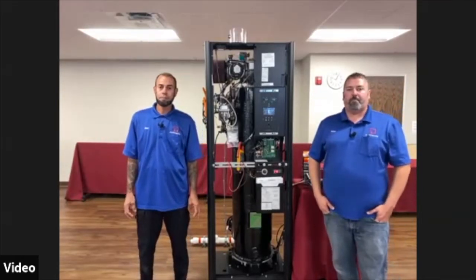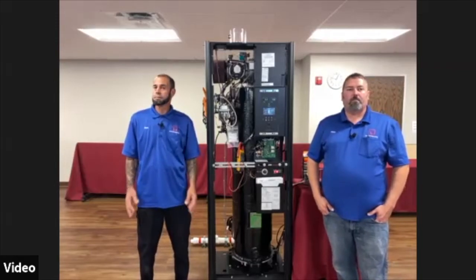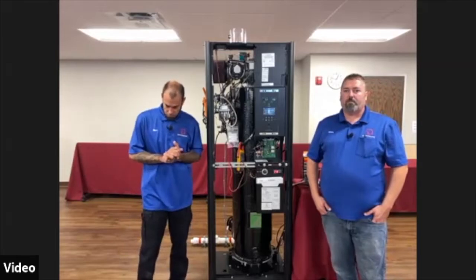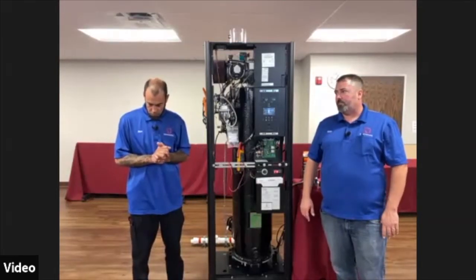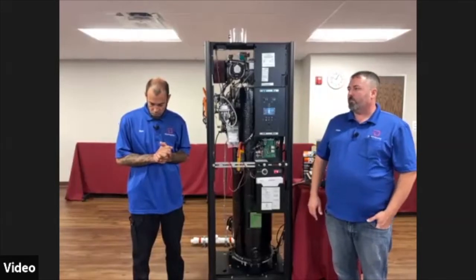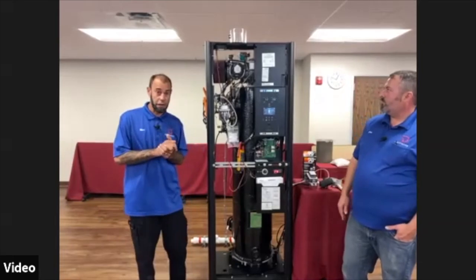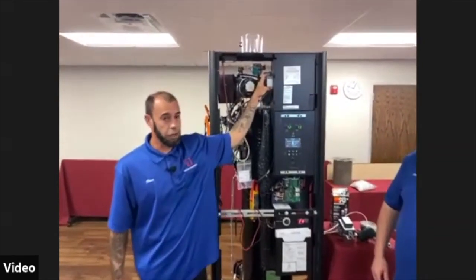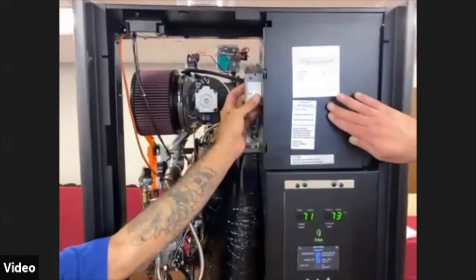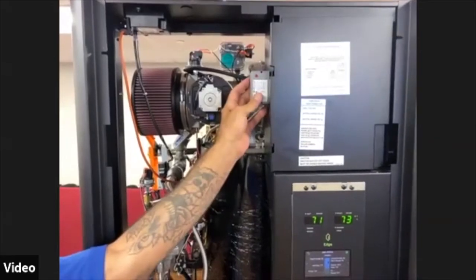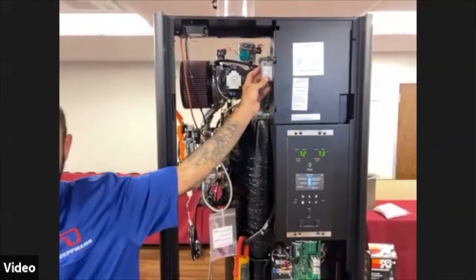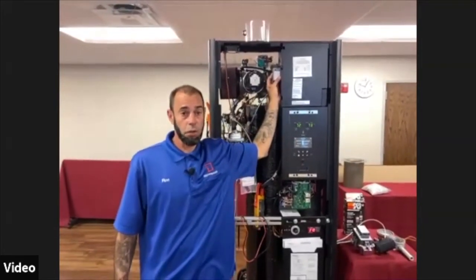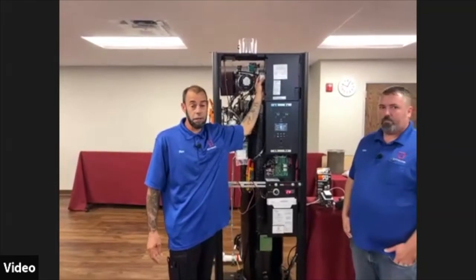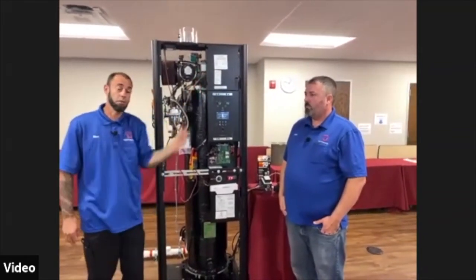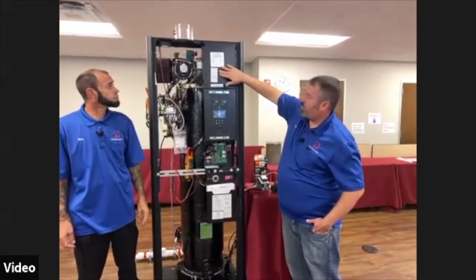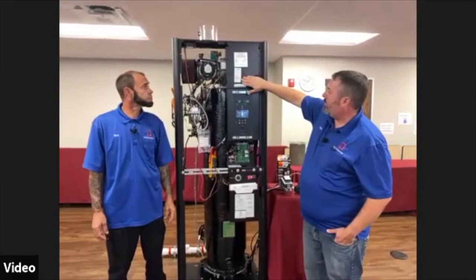All right, and our last question that came in is, if you were piping the boilers in a primary secondary, does the boiler have a built-in relay to start and stop the boiler pump? Yes, it does. This is the relay right here that will start and stop the pump. And you can actually set a pump delay. So you can allow the pump to continue to run for a period of time after the boiler has satisfied its temperature, to pull or extract the remainder of the heat out of the heat exchanger for peak efficiency performance. There's a tag right here that gives you your wire connections on the pump relay for the automation guys to wire into.